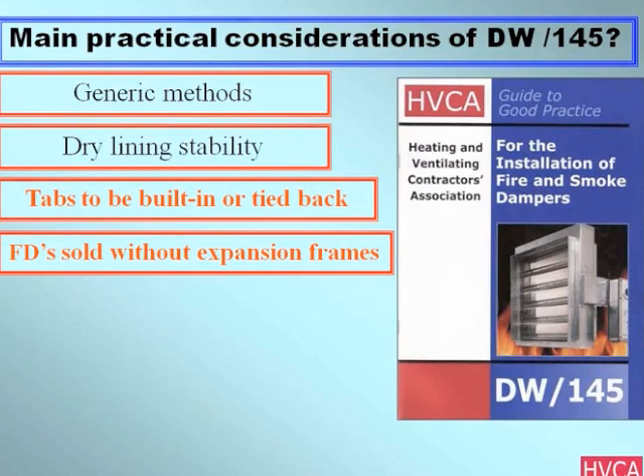All this came from the fact that in the early days of testing fire dampers, unfortunately at one of the test sessions, during the course of the test, the damper fell out of the furnace. They decided the best way to overcome this would be to fasten the damper back to the exposed reinforcing bars in the face of the furnace, and that's where it originated from.